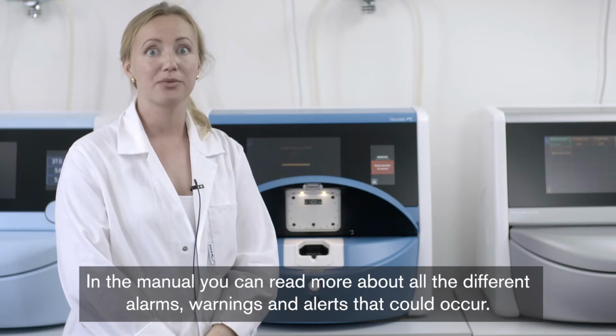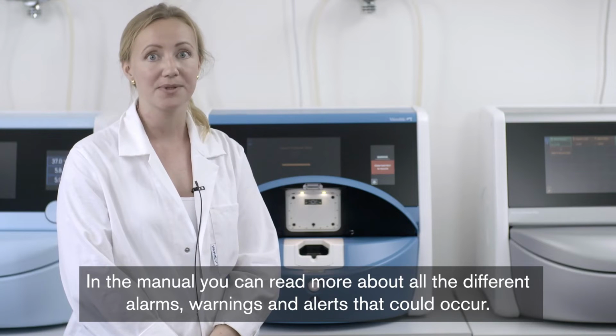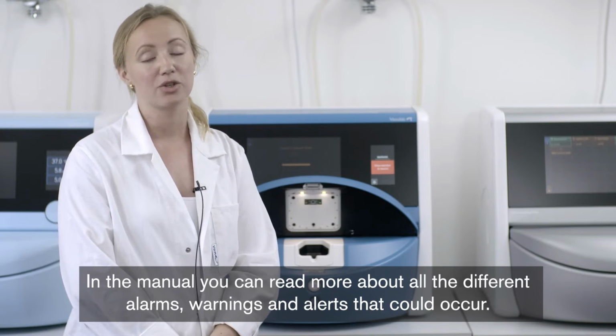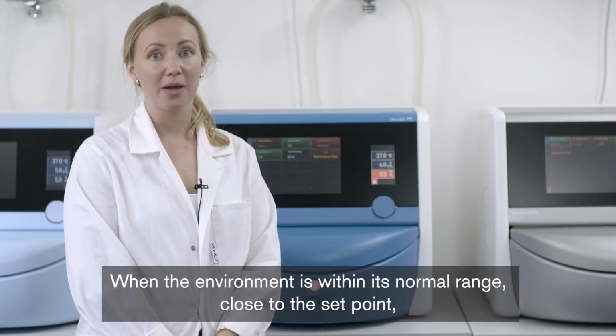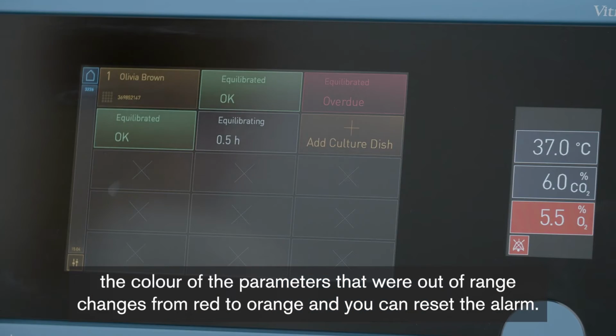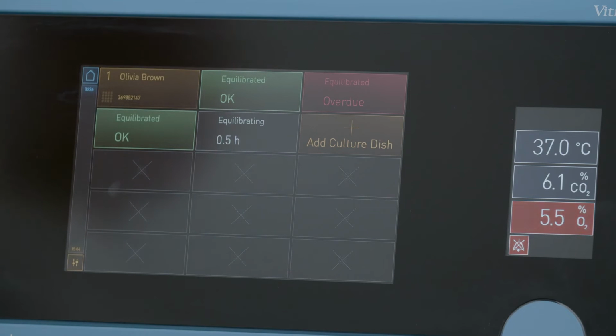In the manual, you can read more about all the different alarms, warnings and alerts that could occur. When the environment is within its normal range, close to the set point, the color of the parameters that were out of range changes from red to orange, and you can reset the alarm.